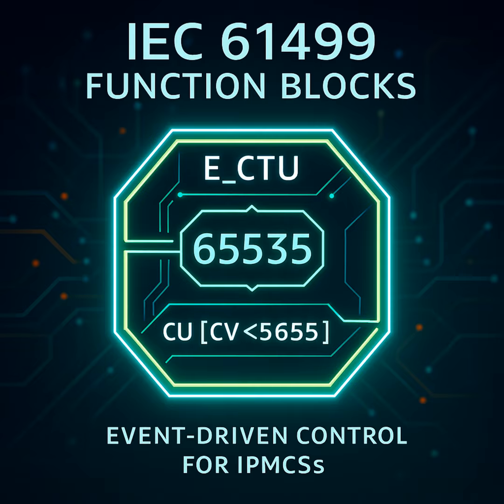and become inaccurate. Exactly. But the ECTU, being event-driven, reacts when the event happens. That CU pulse triggers the ECC and the algorithm immediately, or at least as soon as the resource it's running on can process it, independent of some global scan time. So the count is much more tightly coupled to the physical event itself. Much tighter. And the CUO confirms it happened.